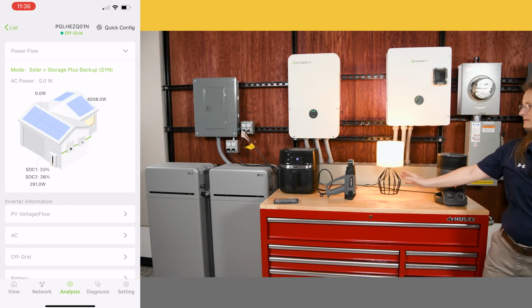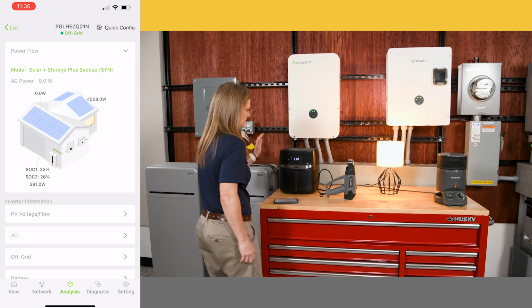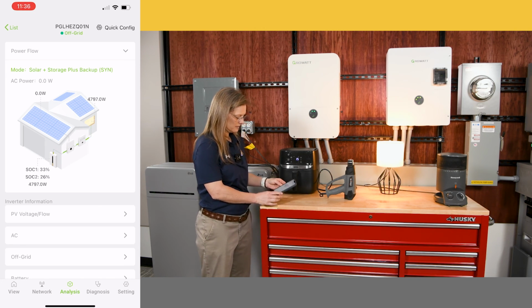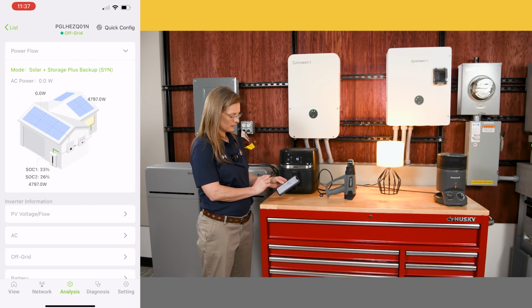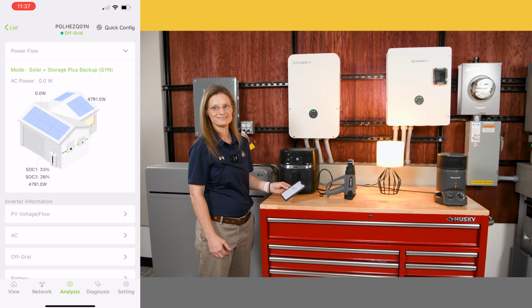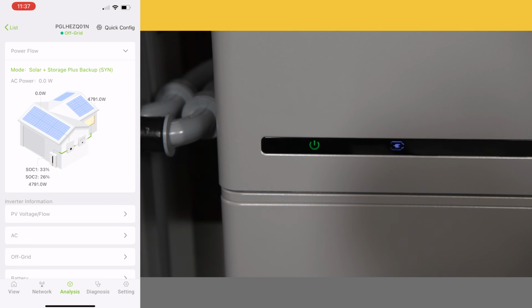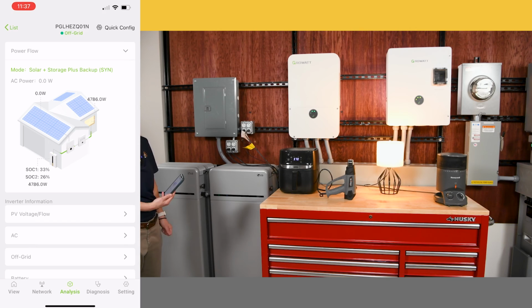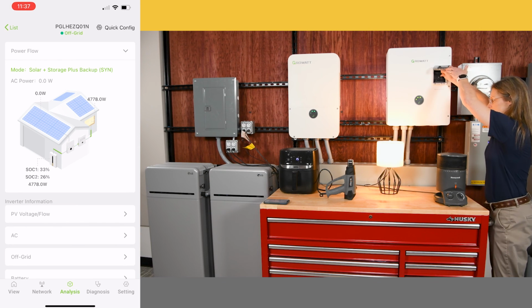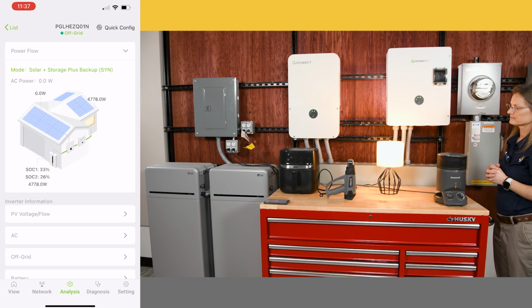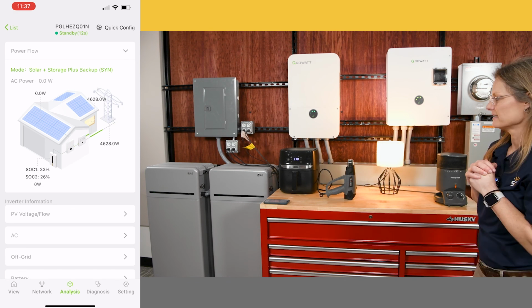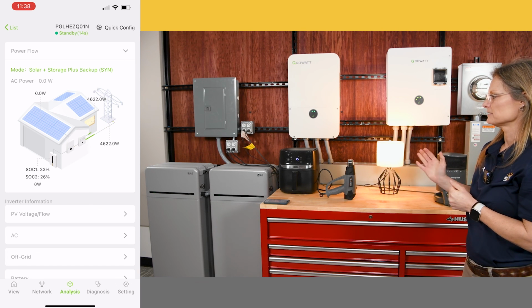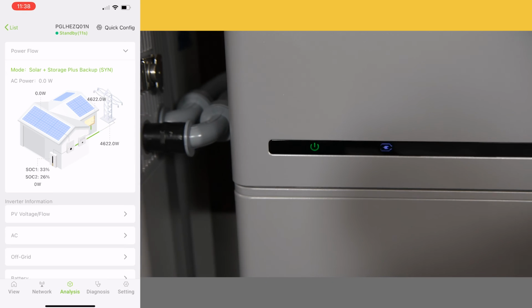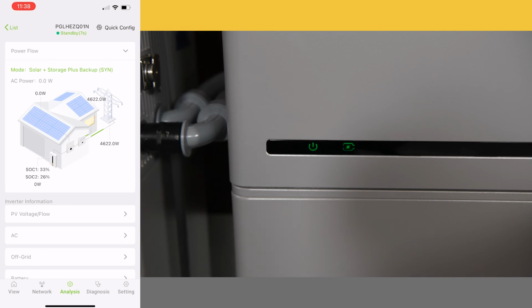The heat is still on, heat gun is still on, light switched over, and our air fryer is still going. And our app shows that we are sending about 4,797 watts from our batteries to power our loads. And we showed a white light on our batteries showing that we're using both of our batteries simultaneously to power our loads. Now, if our grid comes back on, life continues. It takes a few seconds for our batteries to switch back over, but they will begin charging again, and we'll know that when a green light kicks back on beside the power button.